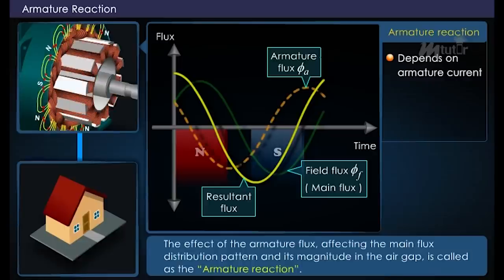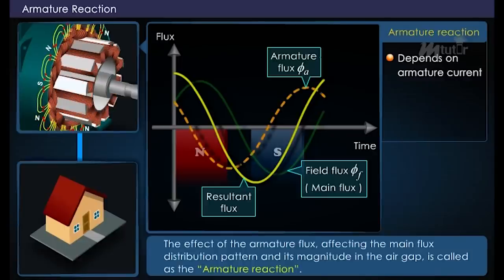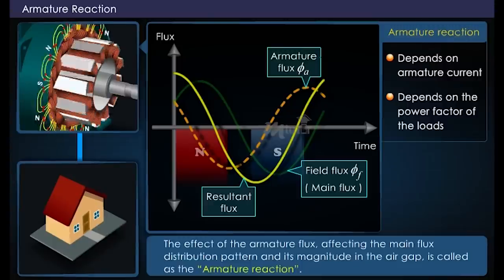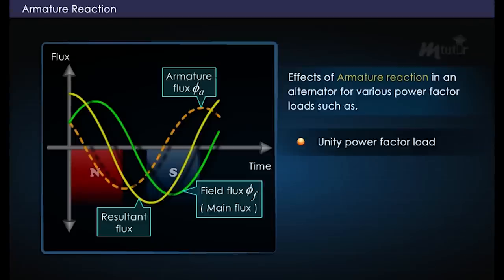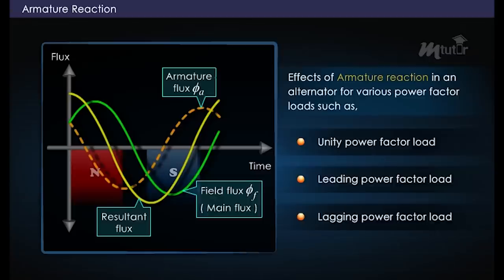This effect of the armature flux affecting the main flux distribution pattern and its magnitude in the air gap is called the armature reaction. The armature reaction depends on the current in the armature, which produces the armature flux, and is also dependent on the power factor of the connected load. Let us analyze the effects of armature reaction for unity power factor, leading power factor, and lagging power factor loads.